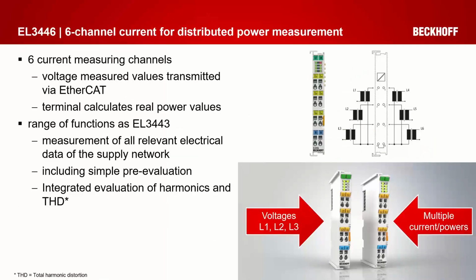So what is this distributed power measurement? We found that our EL3443 is right to measure 3 voltages and 3 currents, but for a distributed power measuring system, we have only one voltage. Typically, we have 1 voltage, but several measurement points for the current. So for this, we have now implemented the EL3446, which allows you to measure 1 voltage but several current measurement points. And at the end, we have the same functionality in one EL3446, but with multiple current measurement points.